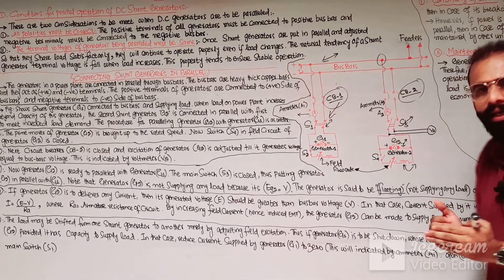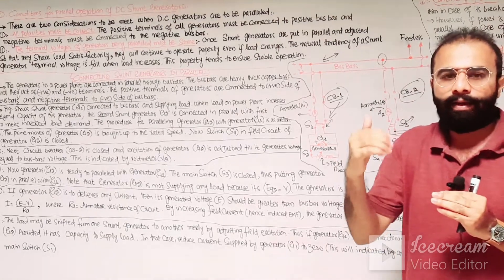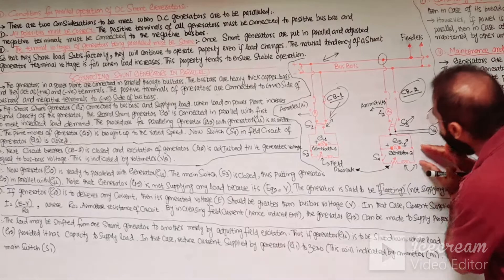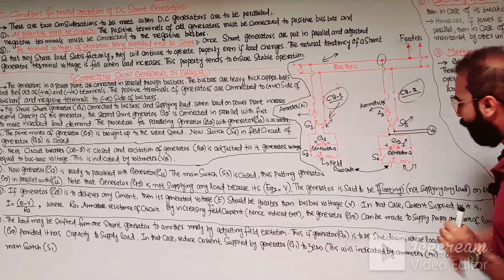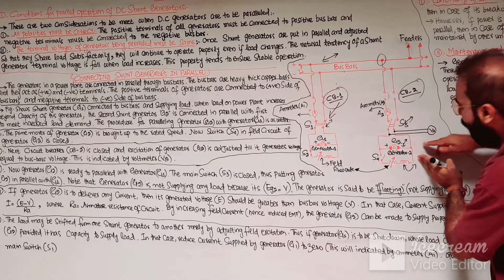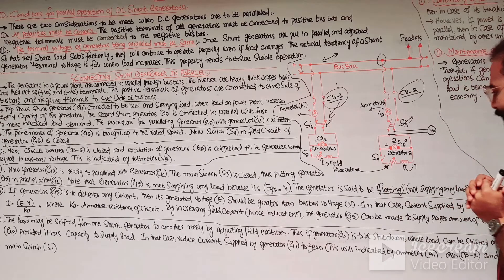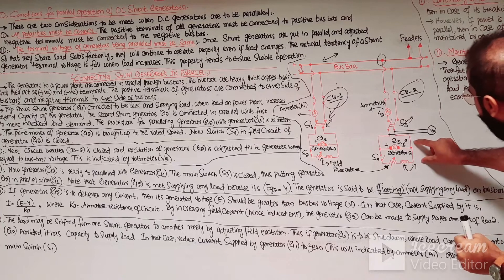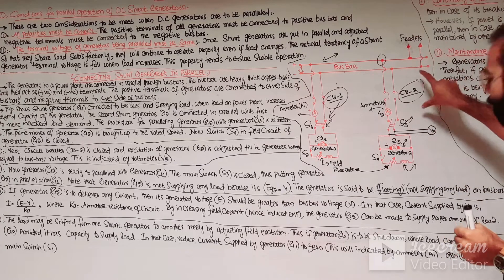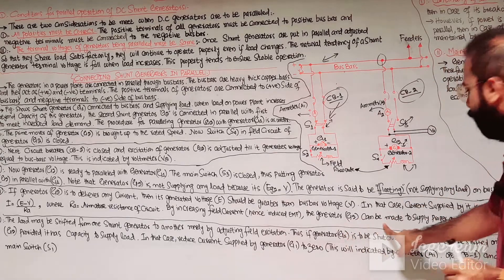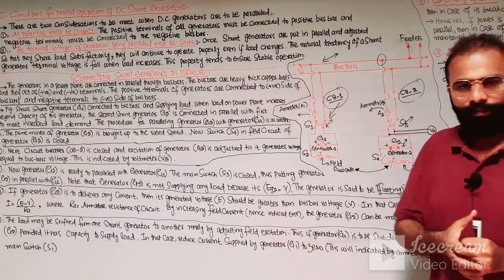To increase the generated voltage of G2, increase the field excitation of the G2 generator. By adjusting the field excitation through the field circuit, the EMF produced by G2 becomes greater than the bus bar voltage, so generator G2 can be made to supply the proper amount of load to the bus bar.